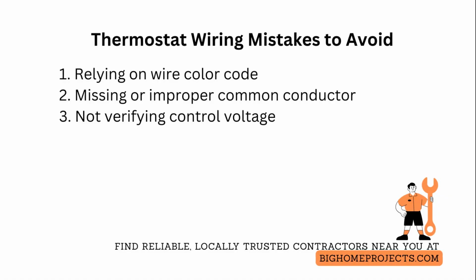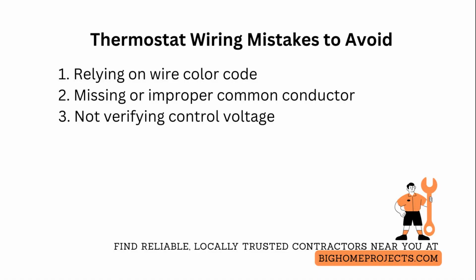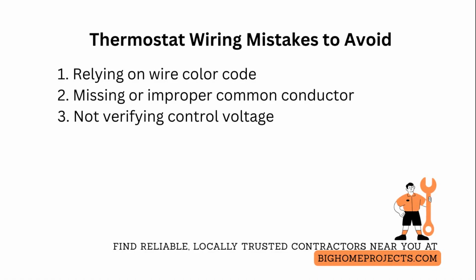One of the biggest mistakes is relying on thermostat wire color code, which causes miswires and furnace lockouts. Fix this by always mapping terminal letters and testing continuity to the air handler before connecting.